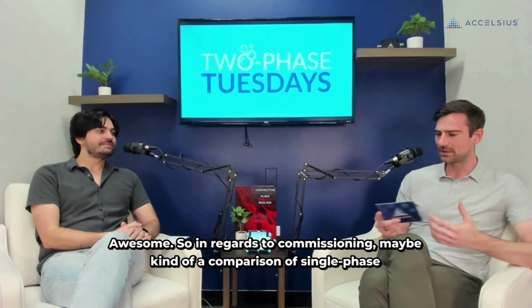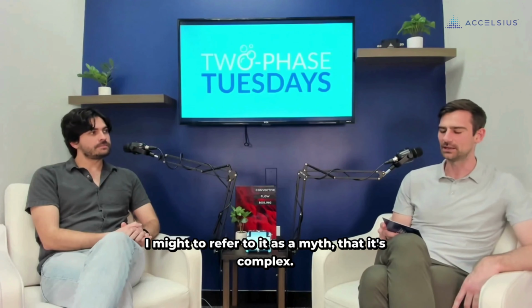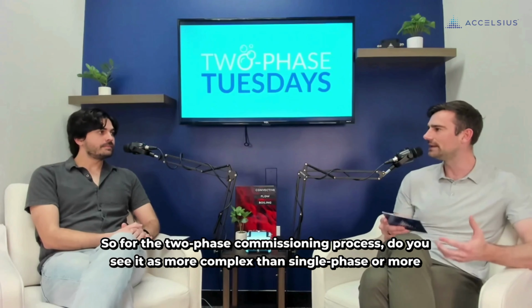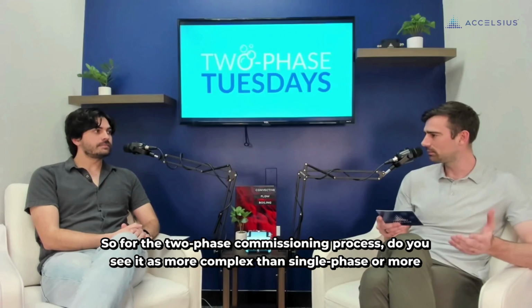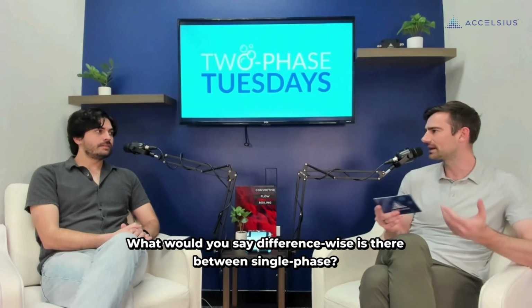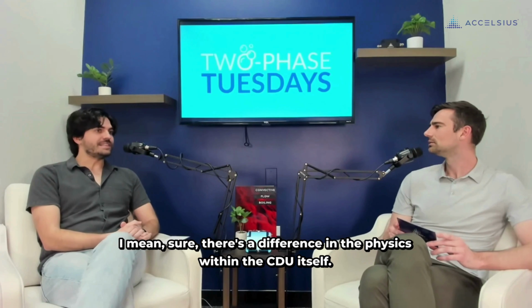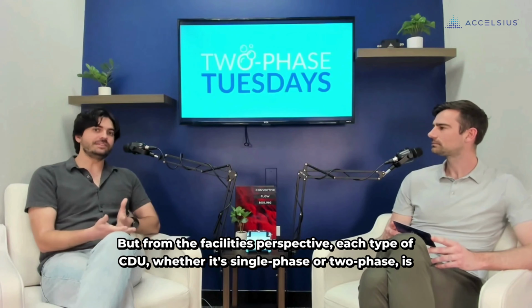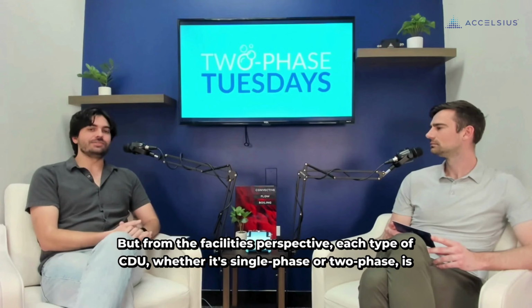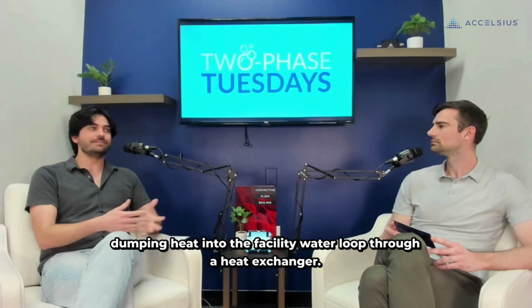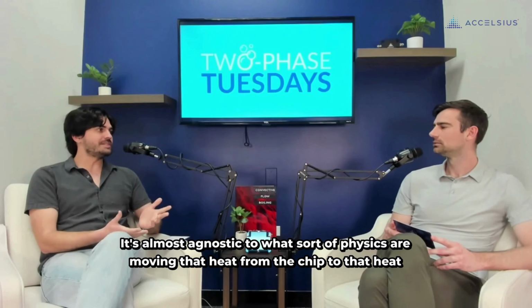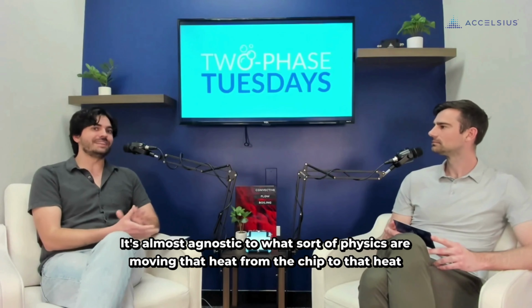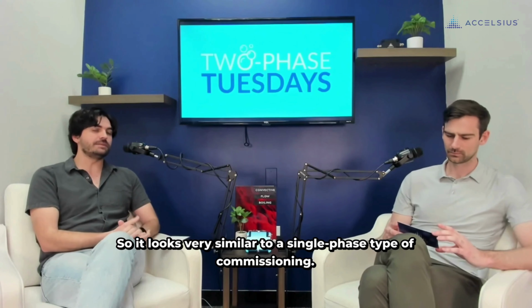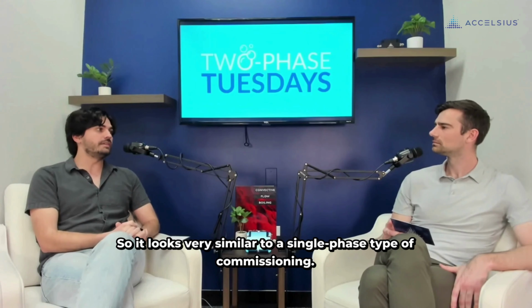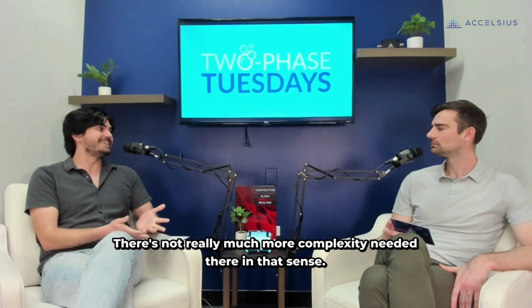So regarding commissioning, let's compare single phase versus two phase. Two phase has the perception, maybe even a myth, that it's complex. For two phase commissioning, do you see it as more complex than single phase, or more critical? There is a difference in the physics within the CDU itself, but from the facility's perspective, each type of CDU, single phase or two phase, is dumping heat into the facility water loop through a heat exchanger. It's almost agnostic to what sort of physics are moving that heat from the chip to the heat exchanger. So it looks very similar to single phase commissioning, and there's not much more complexity needed there.